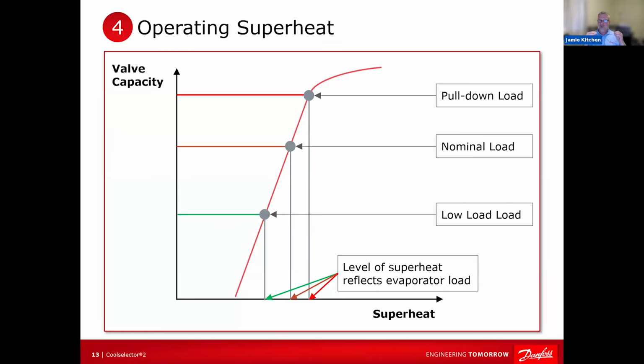So if you're good, you can actually tell how much humidity is in a space just by looking at your evaporator pressure and your TXV superheat, right? Because those are the two main things in air conditioning that give you load, which is your latent heat. Remember when we look at setting superheat and subcooling, what's the indoor value we use? Wet bulb, right? It ain't dry bulb, it's wet bulb. So those are all indications that come together. So the most accurate stroke of this is between nominal load and down below.